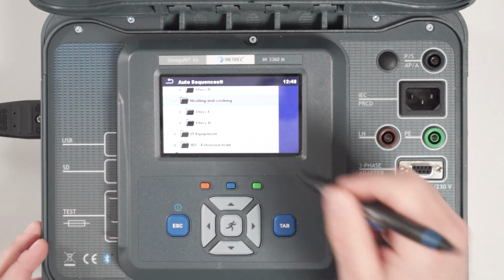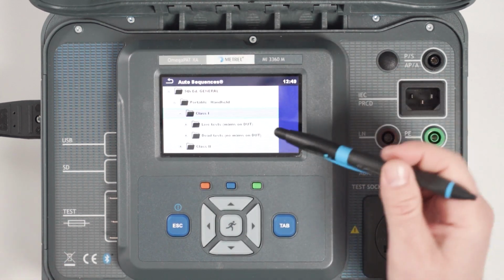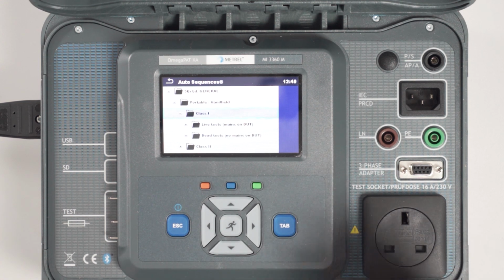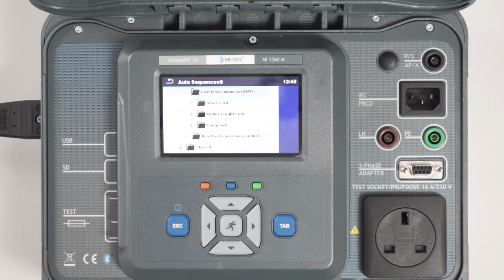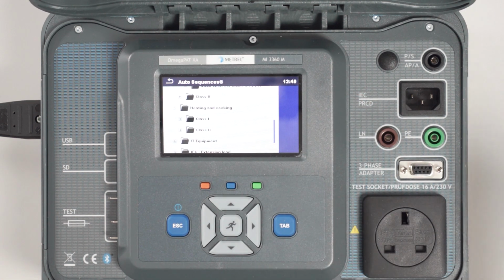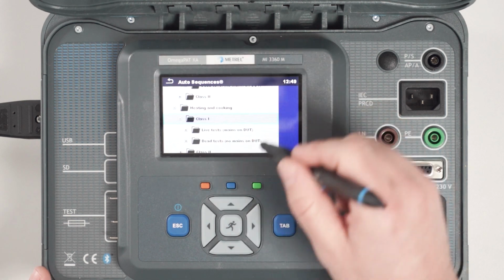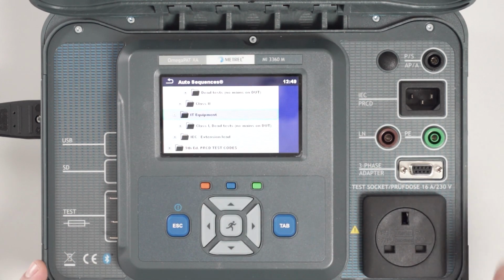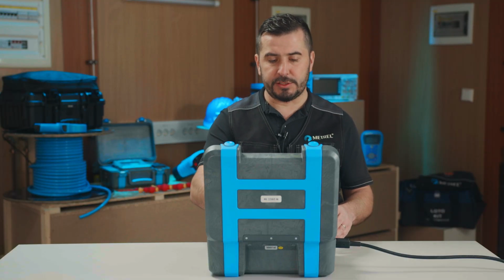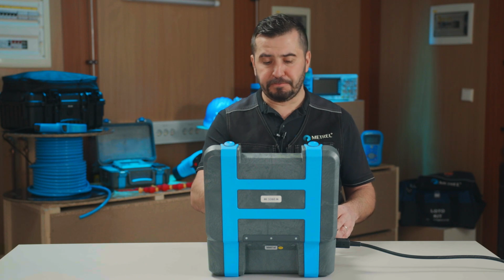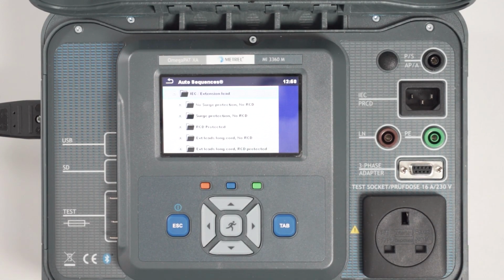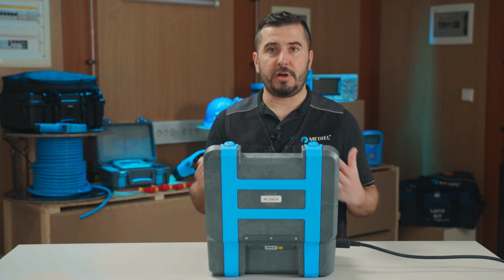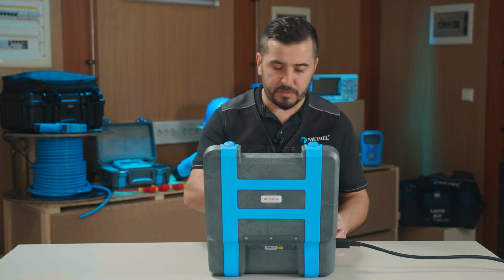It's similar with heating and cooking, though here in the first level we also see that the auto sequences are divided according to live testing or dead testing and per different lengths of the cables of the appliances. Then if we proceed, it's about the same logic for heating and cooking. It's a bit different under IT equipment. Then we have special auto sequences for IEC leads testing, where we can choose between different lengths, whether the appliances are surge protected or whether they have RCD protection. So cables including RCDs can also be tested with this appliance tester.